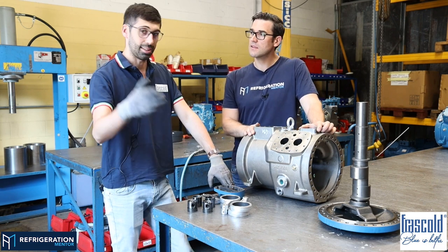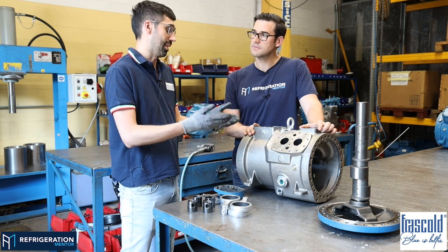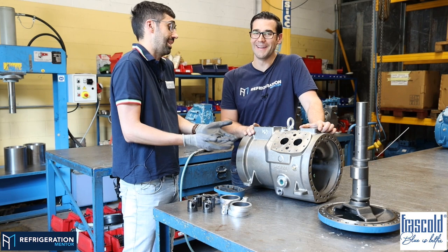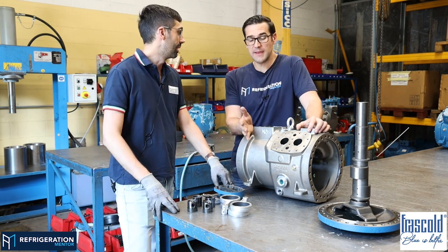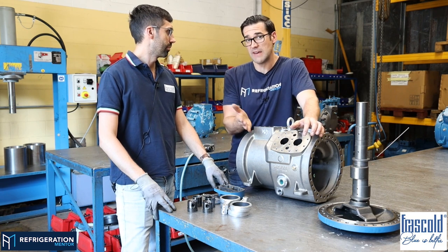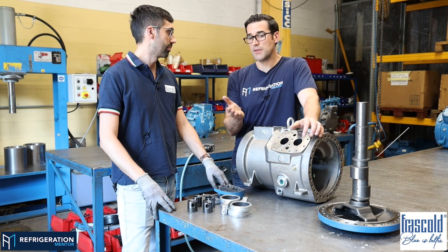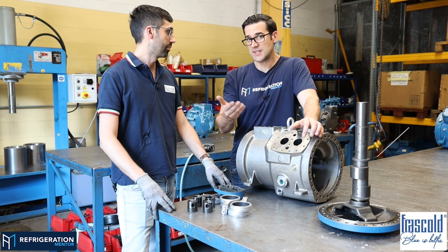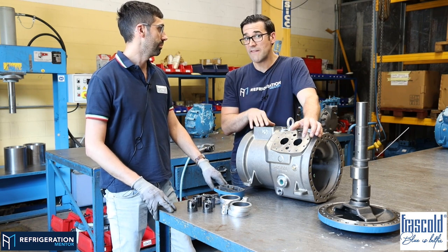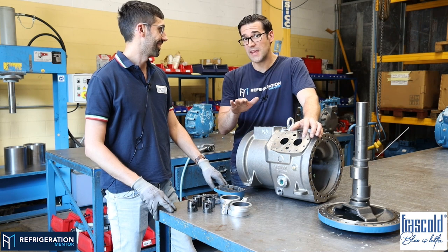There are expert technicians in the field, but youngsters are coming and they must learn, and they must make some mistakes. I've done it. So that's a big thing: not all compressors are dual voltage, but if you have a dual voltage motor, you may have jumpers. If you have a 460 supply, these are US voltages, but you have it jumpered for 230 and then you put 460 on it, game over for that winding.